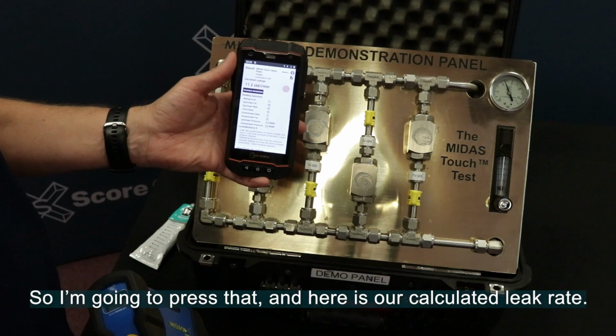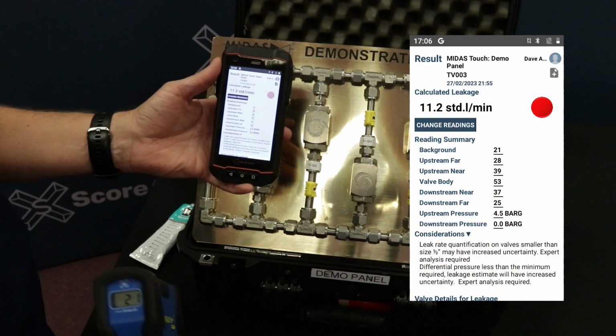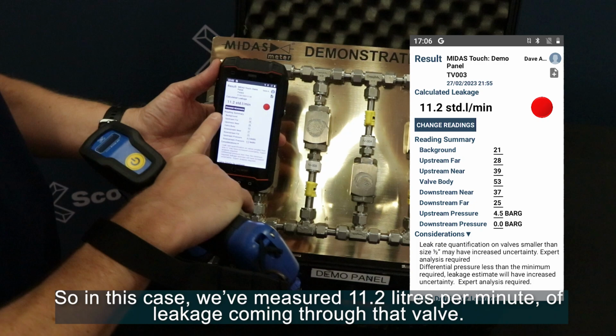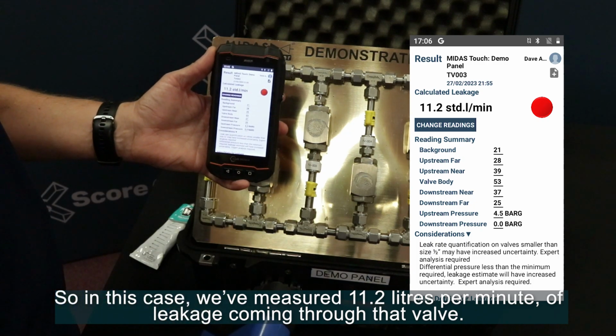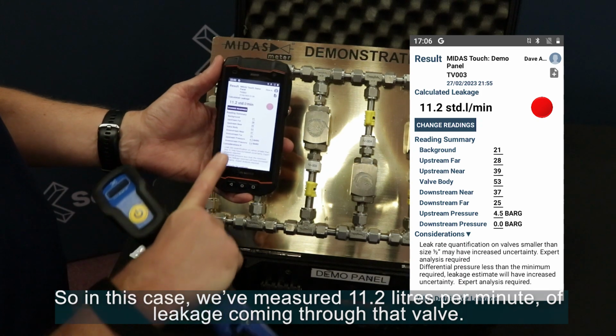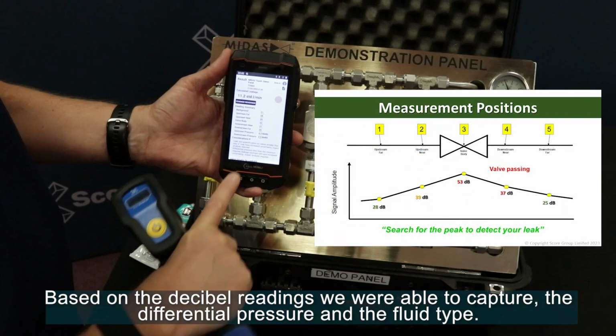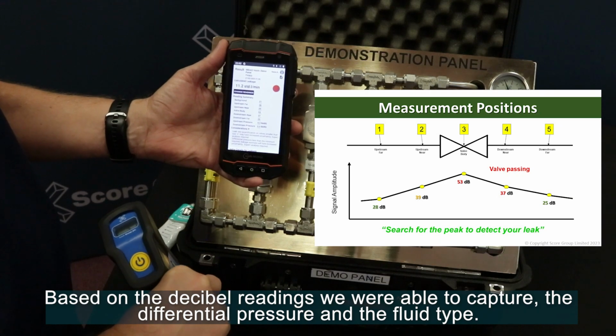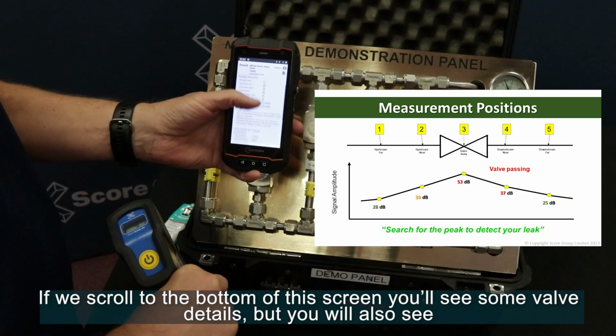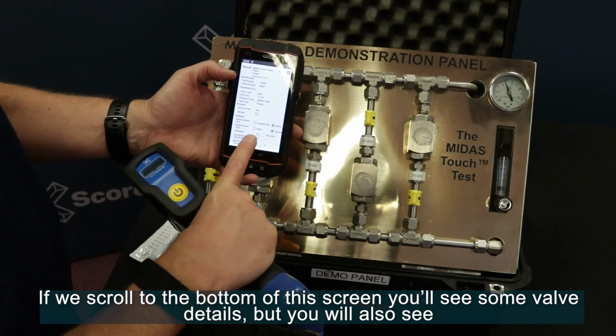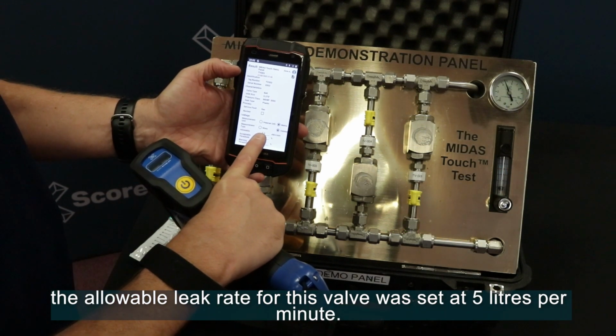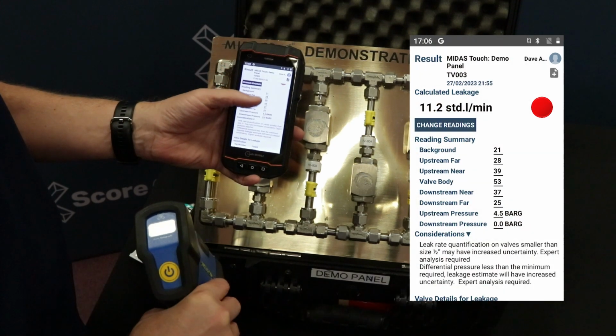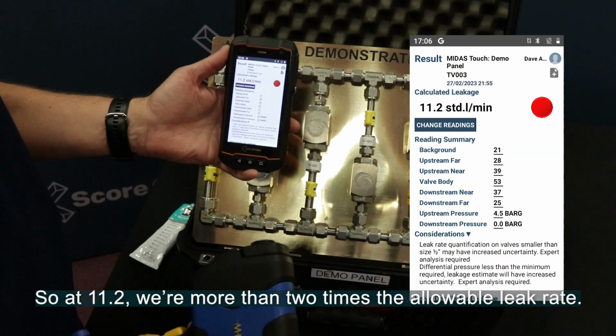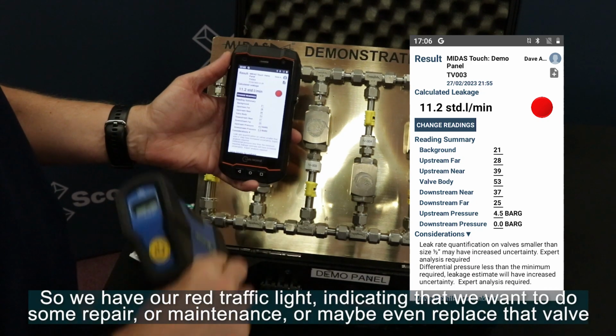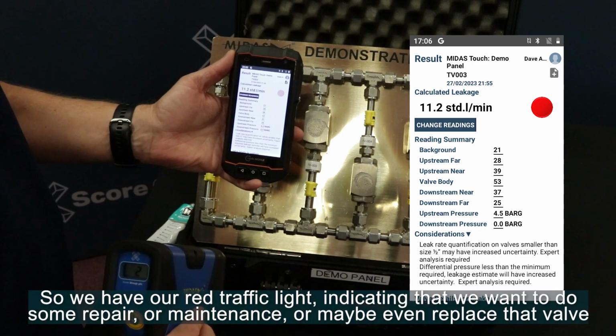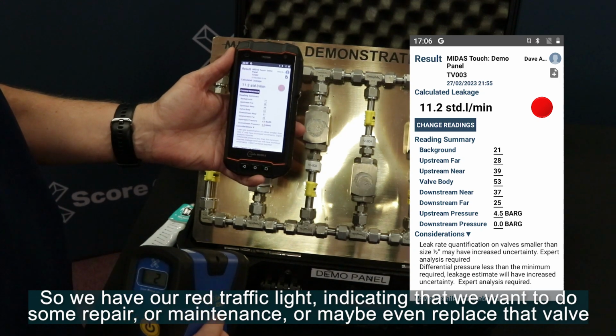So I'm going to press that, and here is our calculated leak rate. In this case, we've measured 11.2 litres per minute of leakage coming through that valve based on the decibel readings that we were able to capture, the differential pressure, and the fluid type. If we scroll to the bottom of this screen, you'll see some valve details, but you'll also see the allowable leak rate for this valve was set at 5 litres per minute. So at 11.2, we're more than 2 times the allowable leak rate. So we have a red traffic light indicating that we want to do some repair or maintenance, or maybe even replace that valve.